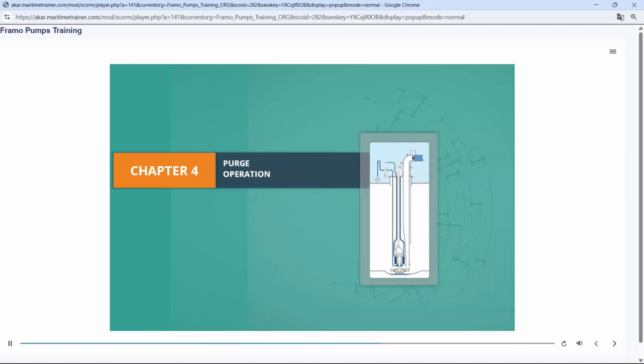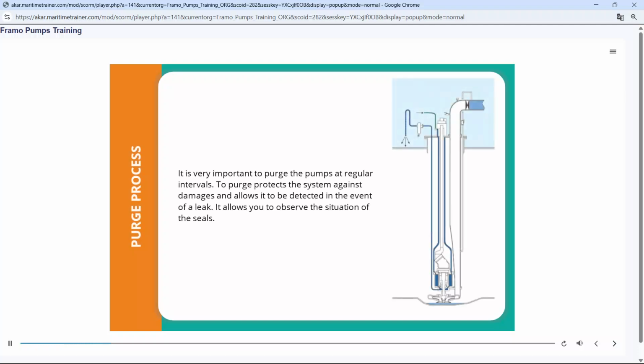Chapter 4. Purge operation. Purge process. It is very important to purge the pumps at regular intervals. Purging protects the system against damage and allows a leak to be detected in the event that one occurs. It allows you to observe the condition of the seals.